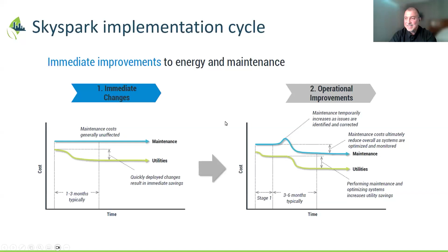Then you start looking at potential energy savings based on optimization - what routines can we implement that provide enhanced energy savings? One would be implementing ASHRAE Guideline 36. For those who don't know, it's a defined set of operating rules to optimize an air handler, VAV boxes, and boiler equipment. It just came out and has been refined. If you have a BAS system, I'd encourage you to ask your operations people to implement those sequences, because the rules and faults are defined in that guide spec.